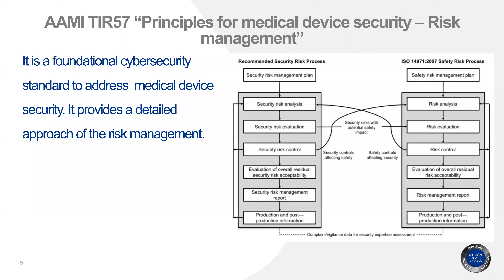The annexes in TIR 57 contain practical methods to implement the risk management process and a list of questions on how to identify security risks, just like safety risks in ISO 14971. TIR 57 supports risk management and refers to 14971 for safety risk management and NIST 800-30 for conducting risk assessments. Note that TIR 57 is not harmonized to EU MDR.